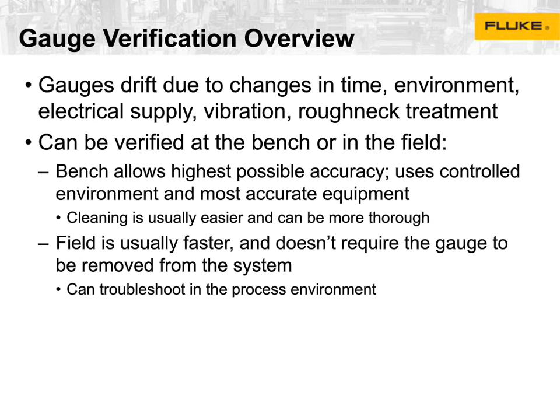It's also usually pretty easy to clean. In the field, the two main advantages are it's probably a little bit faster because you don't have to take the gauge out, and also it doesn't require you to remove the gauge from service, which can be a real problem if you have an explosive gas in there, say methane, and you don't want to just cap the system off, or maybe you can't. Maybe your procedures won't let you. Sometimes if you're troubleshooting, it allows you to troubleshoot in the environment, which is really useful.